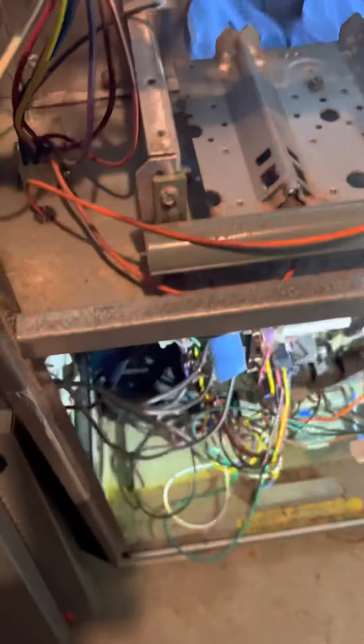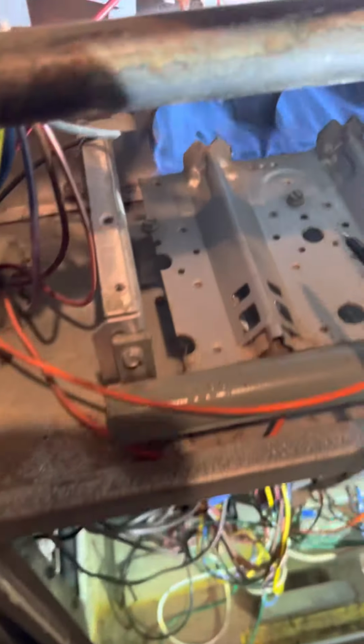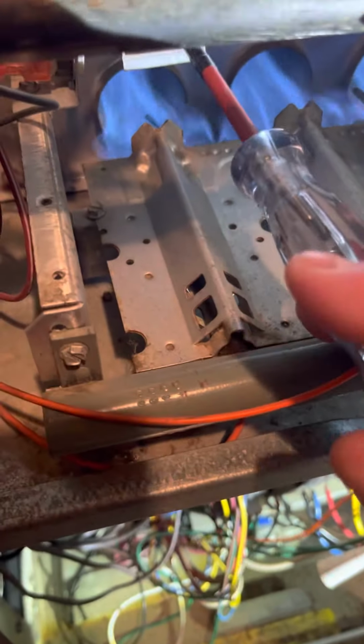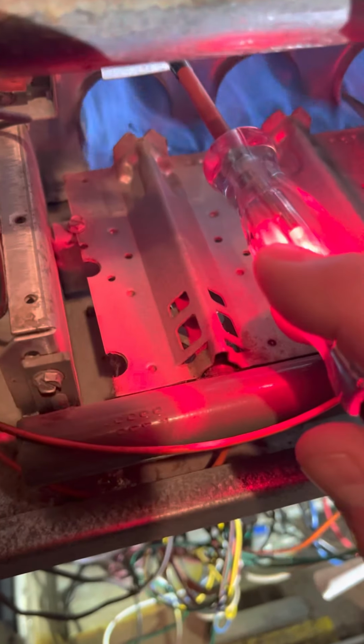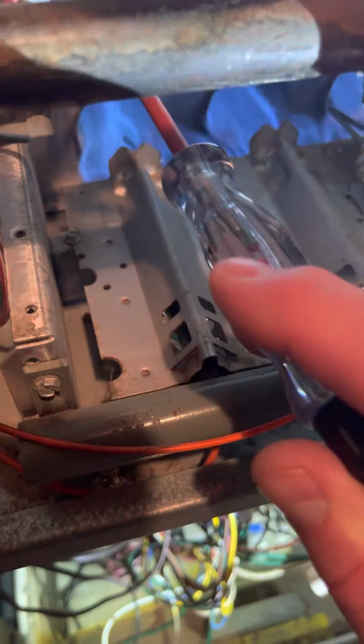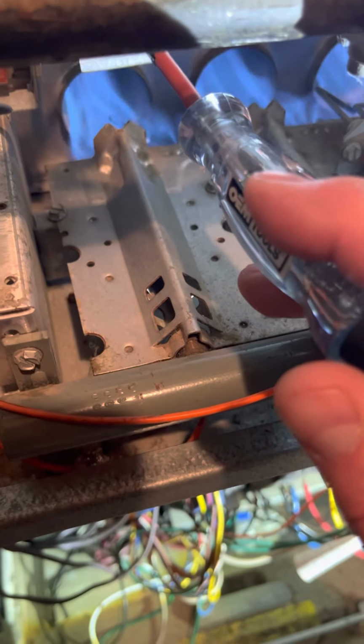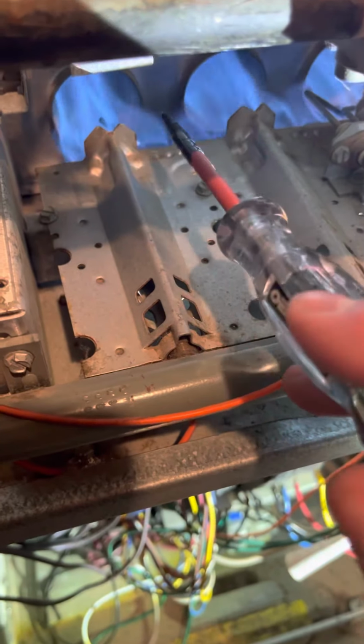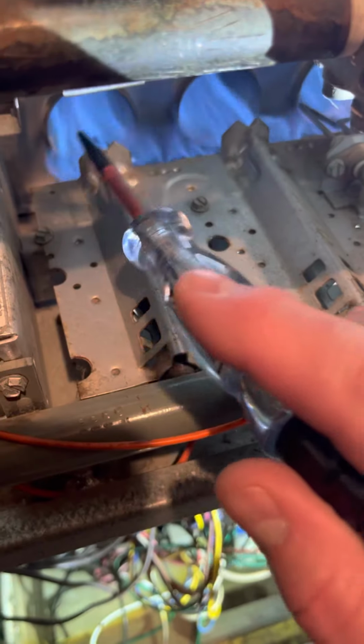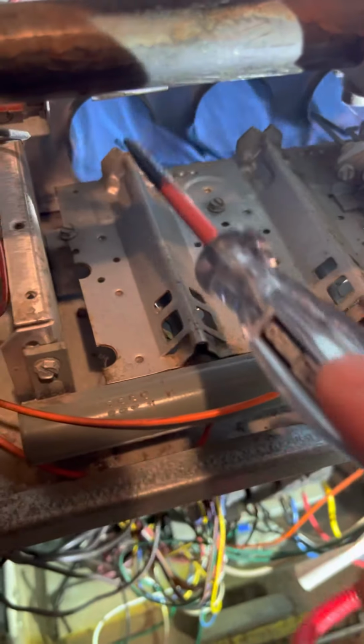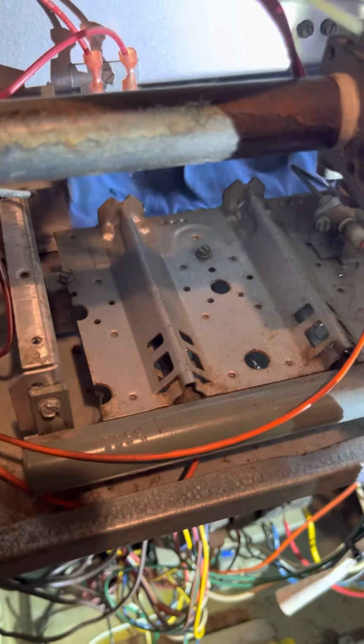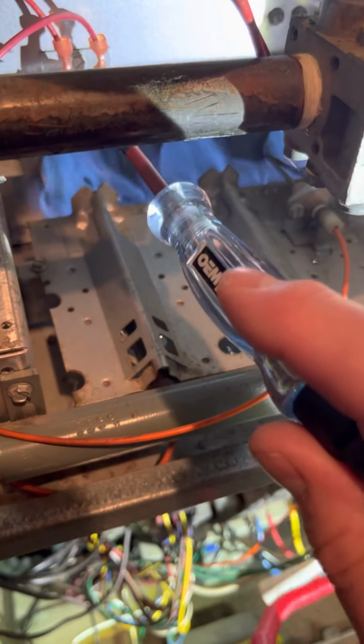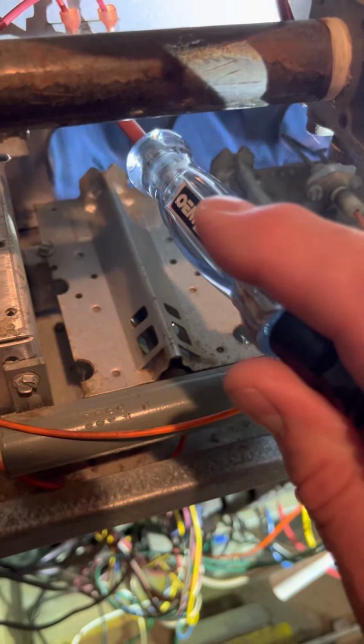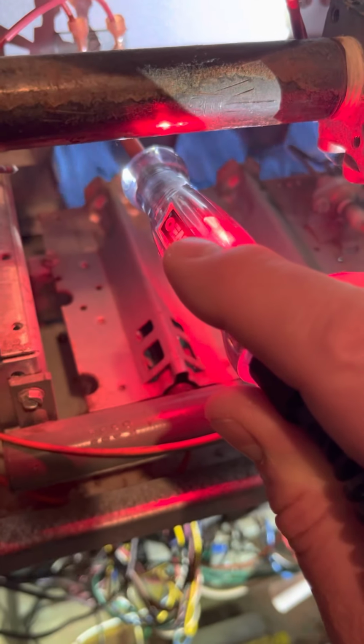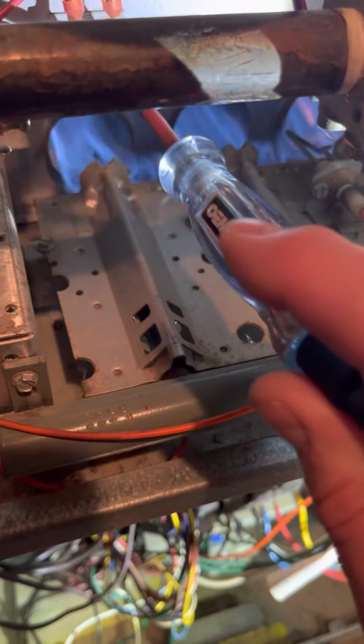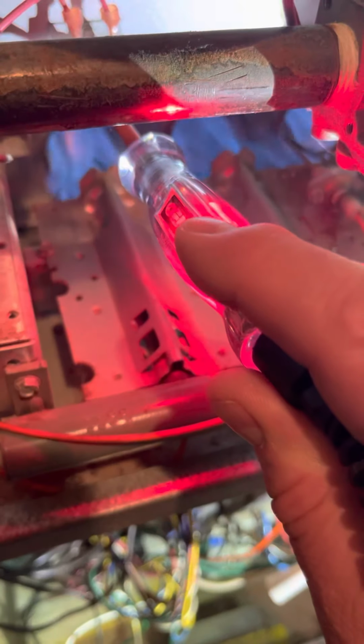We have main burner. So while this was running, we come over here, we have 24 volts. Let's say that this switch went out. Let's say that there's a problem. Let's say I had a bad heat exchanger and the flame wasn't drawing directly in, and it made this switch open. I wouldn't have 24 volts on this side, so I know it's a switch, right? I have 24 volts here, but nothing here.